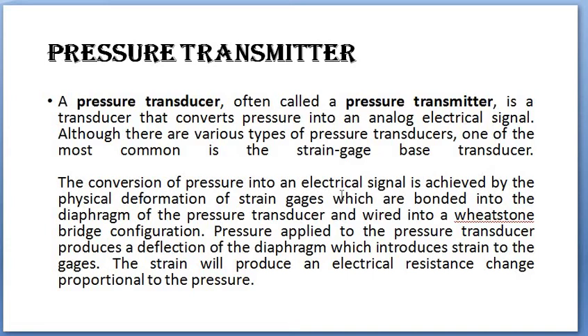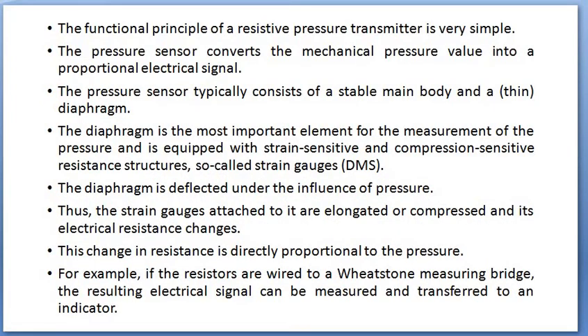Pressure applied to the pressure transducer produces a deflection of the diaphragm, which introduces strain to the gauges. The strain produces an electrical resistance change proportional to the pressure. So the functional principle of the resistive pressure transmitter is very simple.